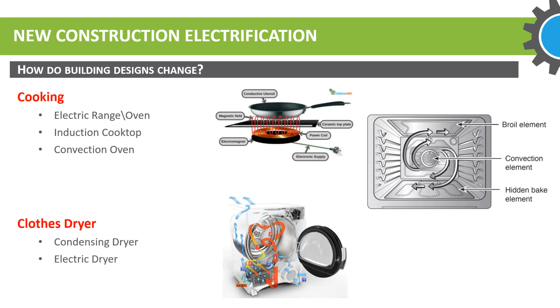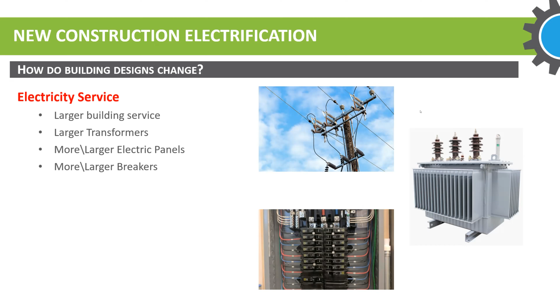Now, when you're looking at going into any sort of electrification, you're increasing your service. You're going to have larger transformers, more panels and larger breakers. That's one thing, like Kyle had mentioned, heavy up, right? You're bringing more demand of electricity into your building, so you need to make sure you have the proper electrical services for that building. And if not, you have to bring it in. So let's go to the next one.